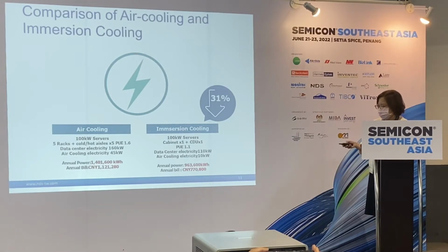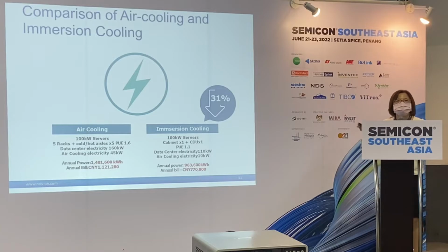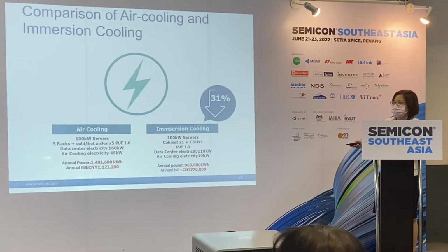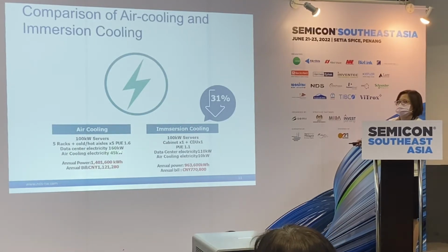For air cooling, it might require 5 racks. And because you need to separate the hot and cold air, they need aisles. So they might require 5 aisles. In this way, the best PUE they can do is 1.6. But let's look at the electricity. 160 kilowatts will be consumed for the data center electricity. For the air cooling electricity, it will be 45 kilowatts.